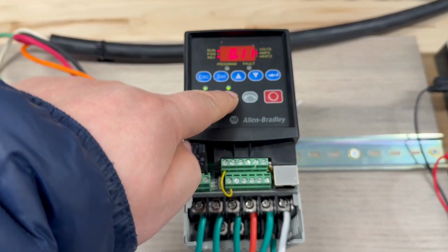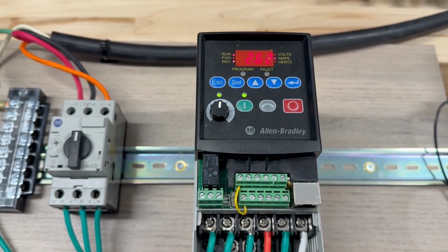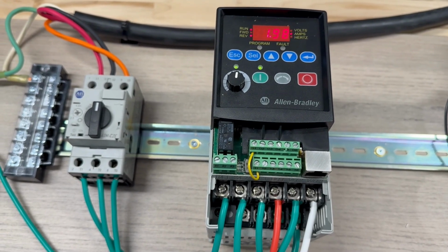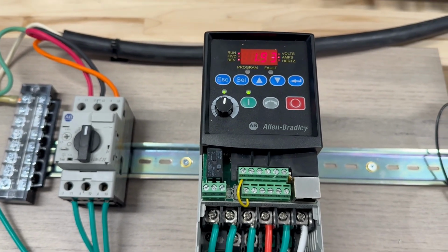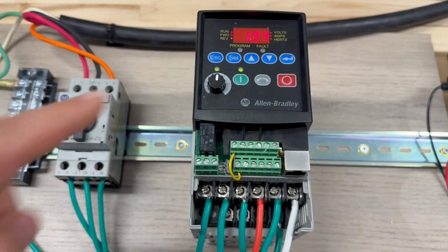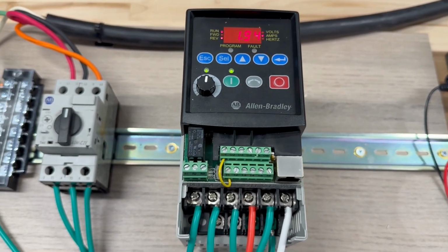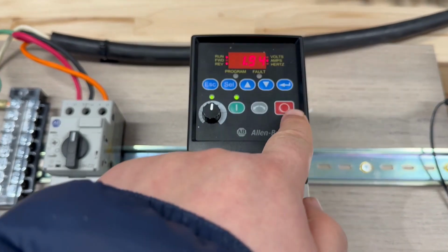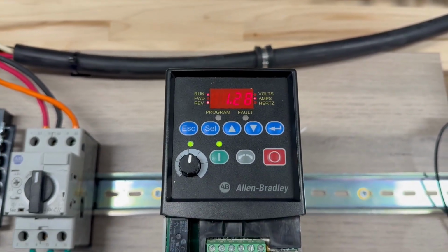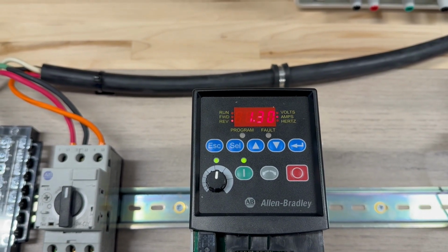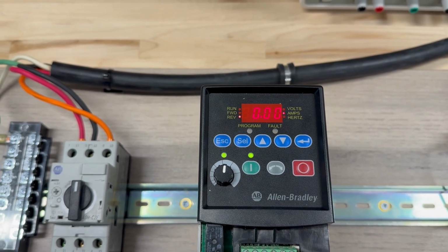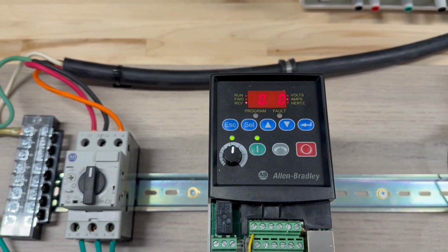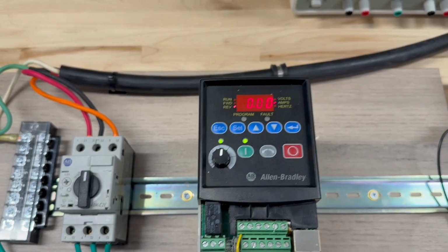Let's start the motor. As you see, it goes up, the current goes up. So I think my frequency should be around 25 or 30. Now I get to the max frequency that I adjusted with this variable resistor. Now let's stop. It goes down, and see now it injects that 1.3 that we had, and you will actually see it keep that for 5 seconds.